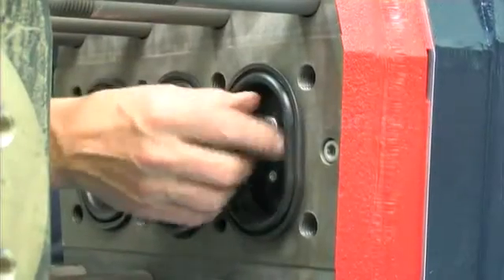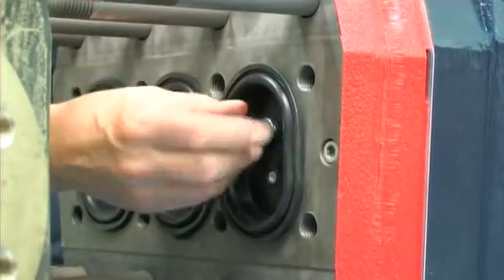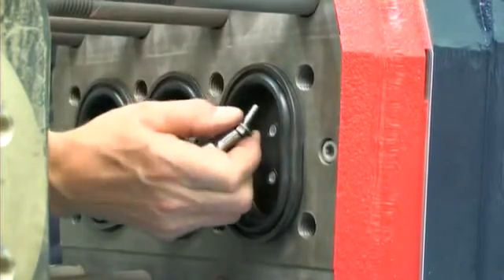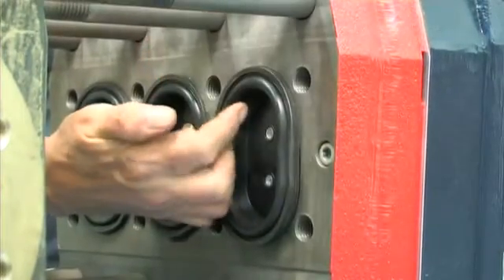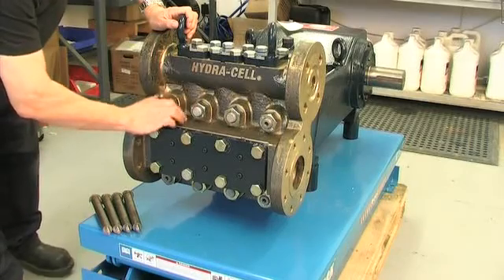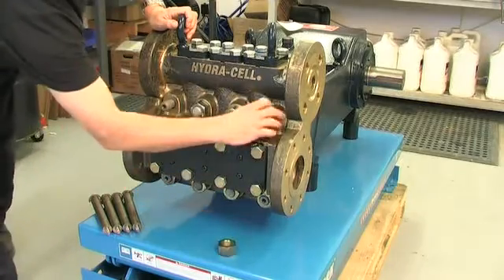Replacing diaphragms. With T-Series Hydra-Cell pumps, diaphragms can be replaced in the field. But it is important to understand that a ruptured diaphragm generally indicates a pumping system problem, and replacing only the diaphragm will not solve the larger problem. To replace a diaphragm, first disconnect the piping and drain the pump of oil.